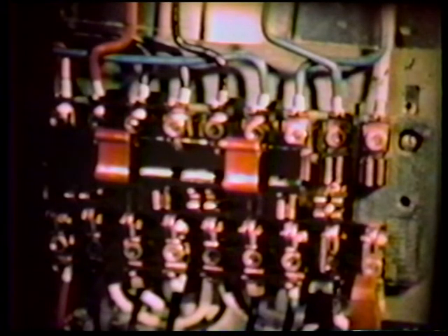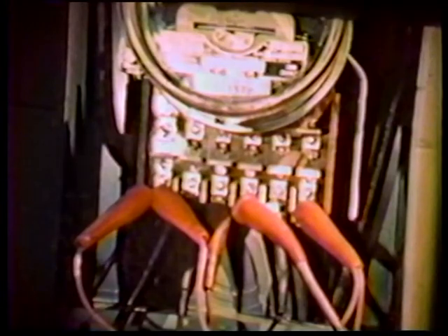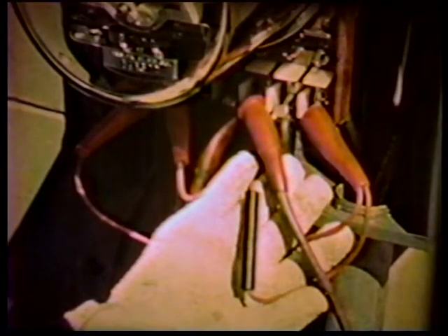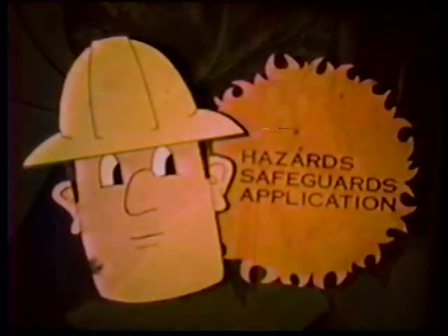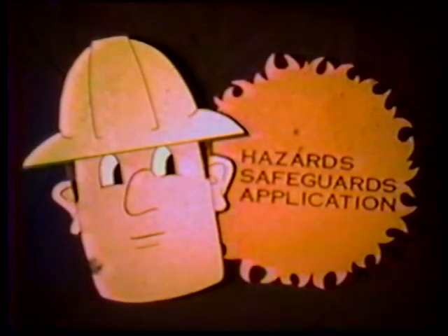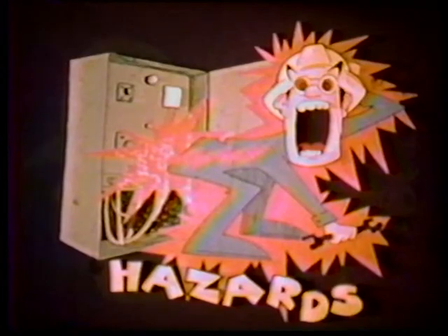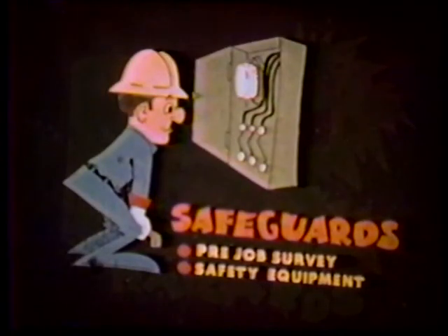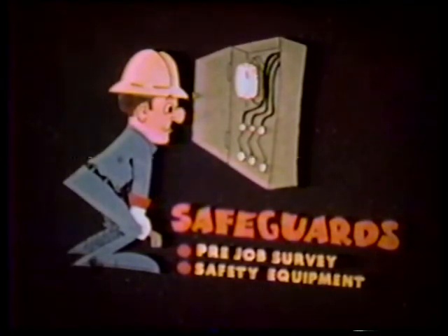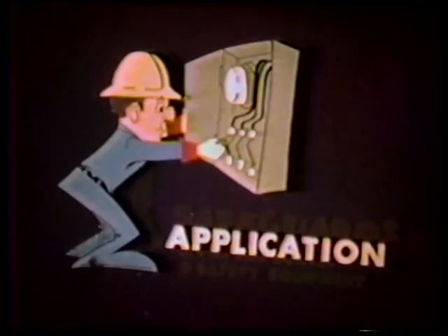When testing, the meterman needs to remember that energized and grounded parts are very close together on test switches and test jacks. Use fused leads to minimize fault current when shorts or grounds occur. Now let's summarize what we've discussed. We've discussed the hazards you will encounter, the safeguards you can use to keep these hazards from becoming an accident, and some applications showing how these safeguards can be applied to job situations.